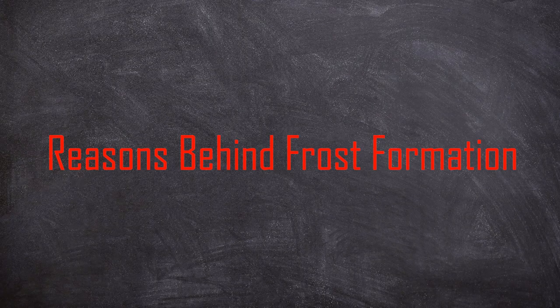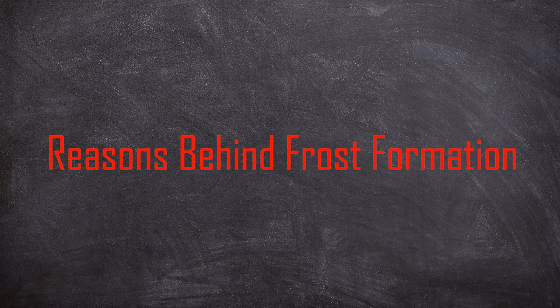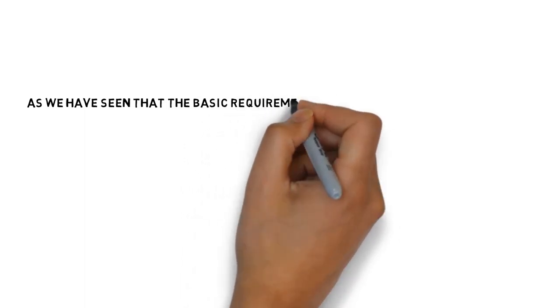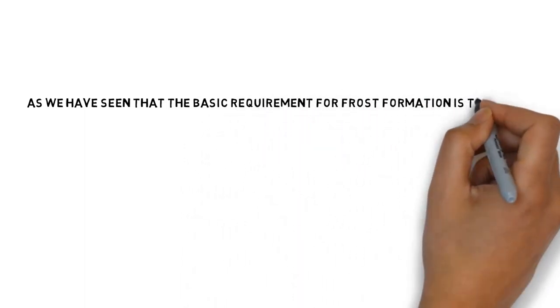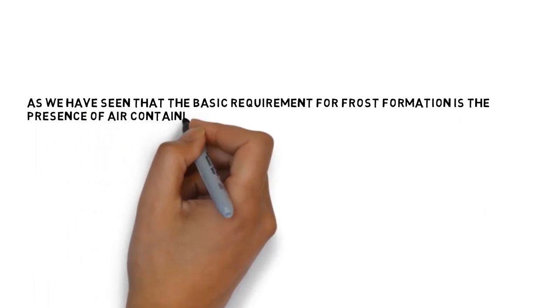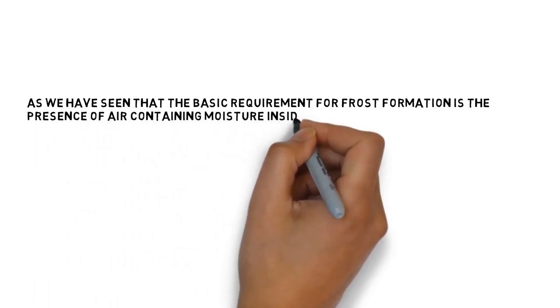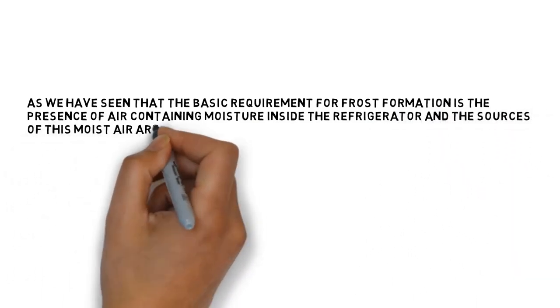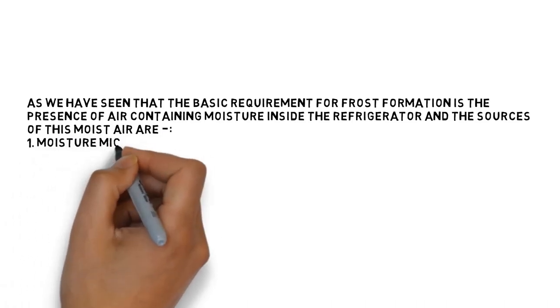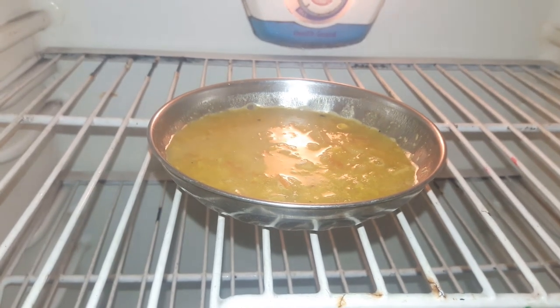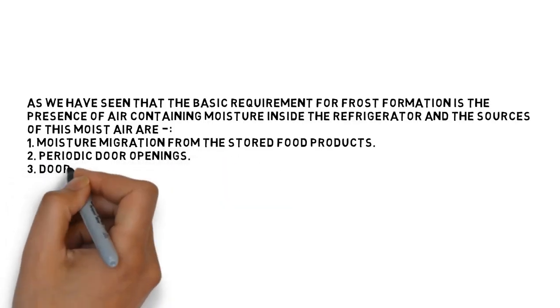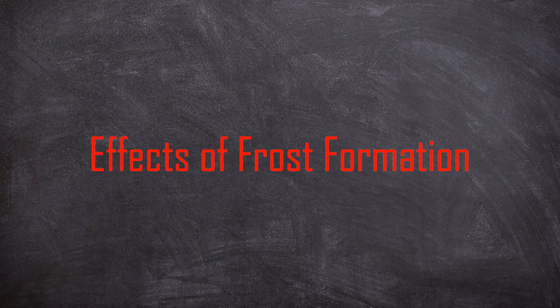So what are the reasons behind this frost formation? As we have seen, the basic requirement for frost formation is the presence of air containing moisture inside the refrigerator. And the sources of this moist air are: number first, moisture migration from the stored food products; number second, periodic door openings; and number third, door gasket leakage. So what are the effects of this frost formation?